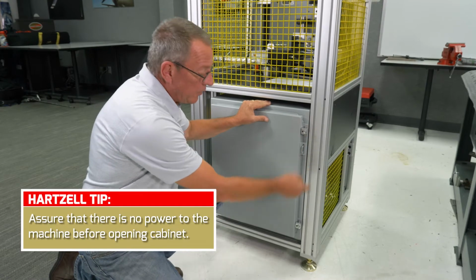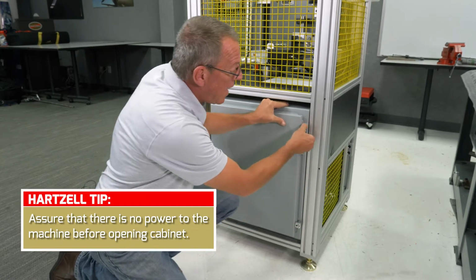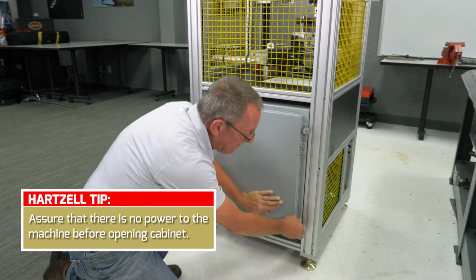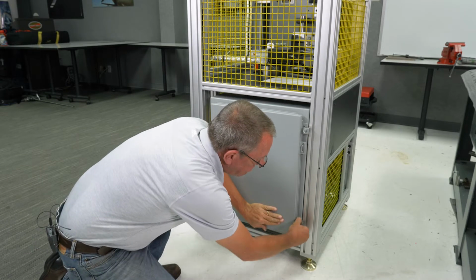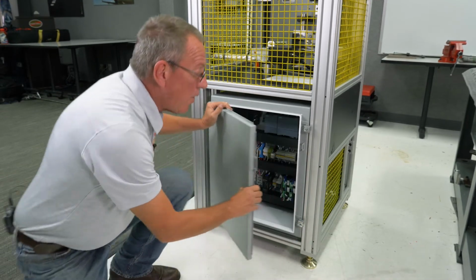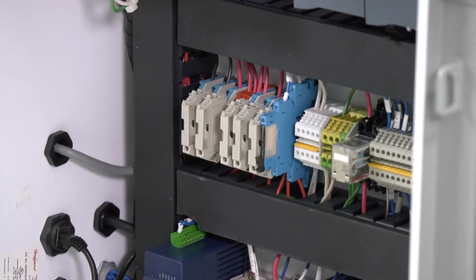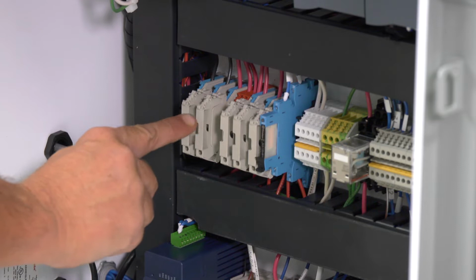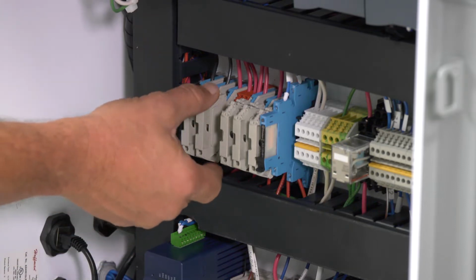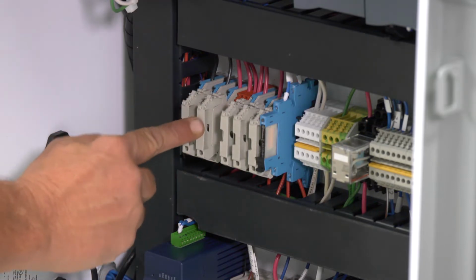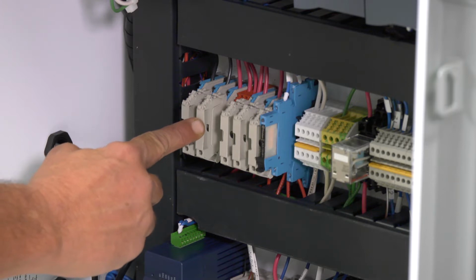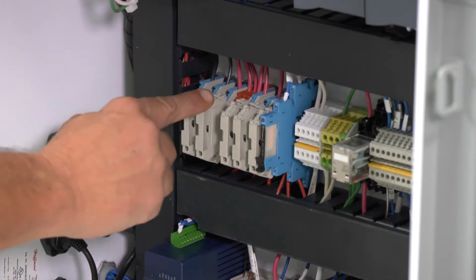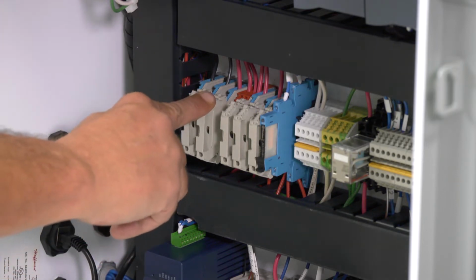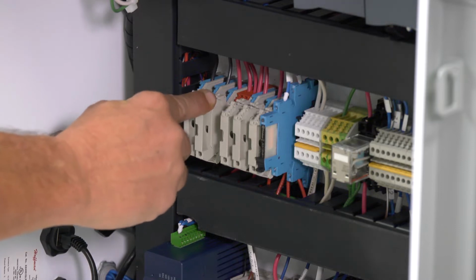So to open the fuse panel, you'll need to loosen these two screws and then pull the clips back, which allows the door to open. Inside we'll find the fuse panel, and you'll see this fuse block. This fuse block here is in the 110 to 127 volt position. This will be the position of the fuse block as the machine is shipped.